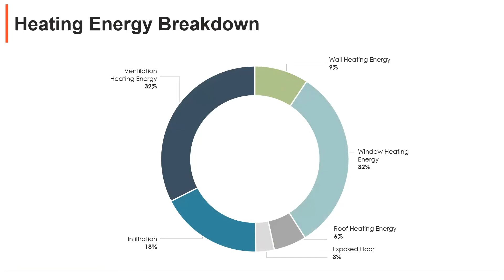But here is your passive approach system. So we now have operable windows instead, with a green LED light to say that it's a good time to open up the windows, and then a heat pump thermostat to keep us regulated. For this project specifically, they did not. Originally we were talking about disabling the HVAC unit when the green light was on, but they didn't have open/closed statuses. They're manually operated, with no status of whether it was open or closed. If you wanted to turn off the heat pump, I would recommend having a contact closure, sort of like one of your security devices on those operable windows, to be able to do that and turn off the equipment.